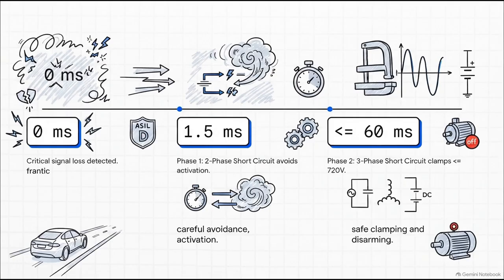At 0 milliseconds, critical signal loss is detected. The motor is flying blind. By 1.5 milliseconds, phase 1 activates, triggering a two-phase short circuit that carefully avoids a massive destructive surge of current. And then, in just 60 milliseconds maximum, phase 2 finishes up. The system drops into a three-phase active short circuit, safely killing the motor torque and keeping that dangerous surging DC bus voltage clamped tight below 720 volts. It literally catches a failing motor and disarms it safely in fractions of a second.